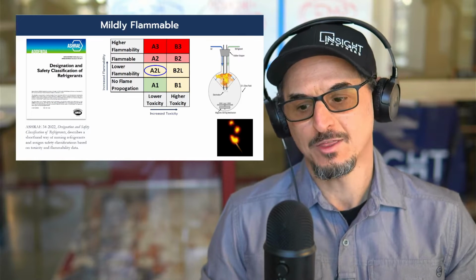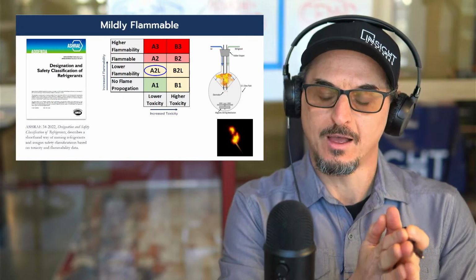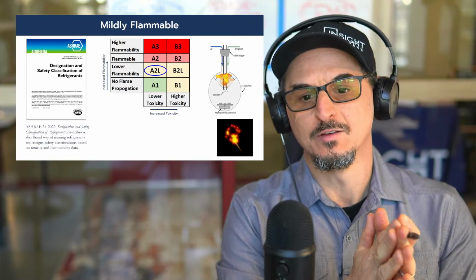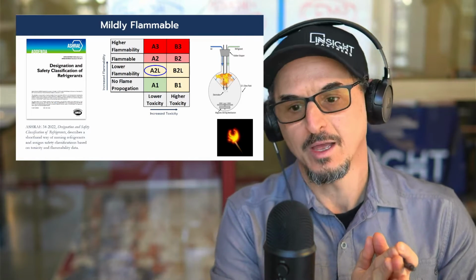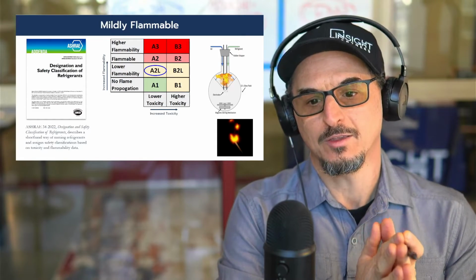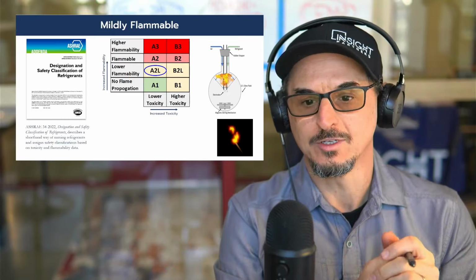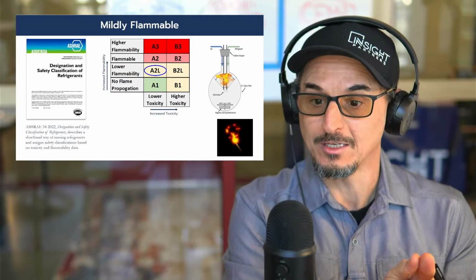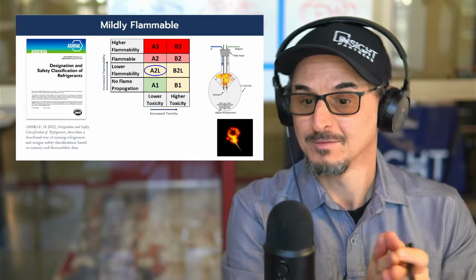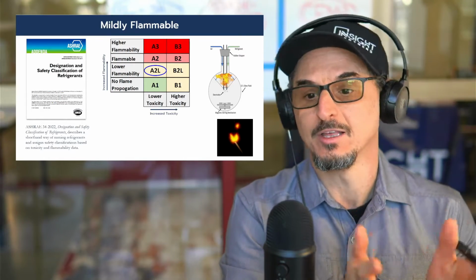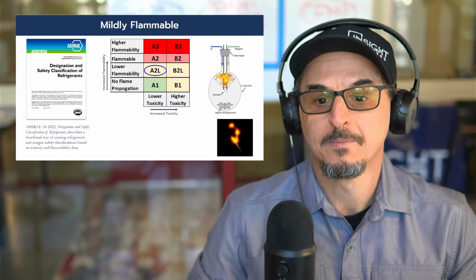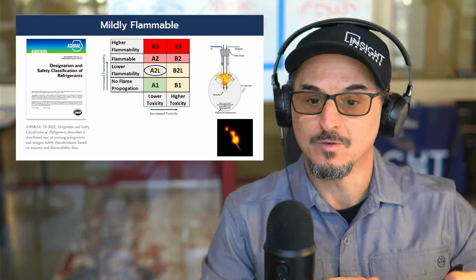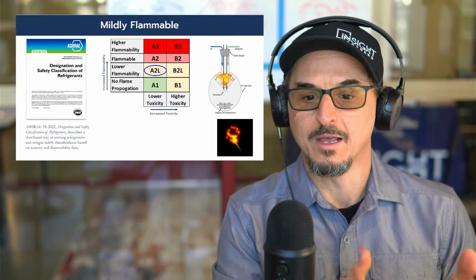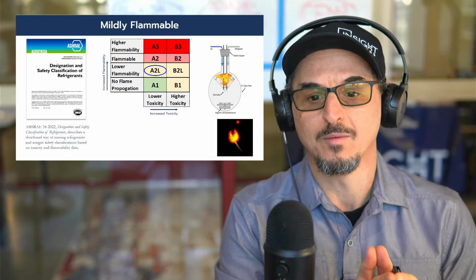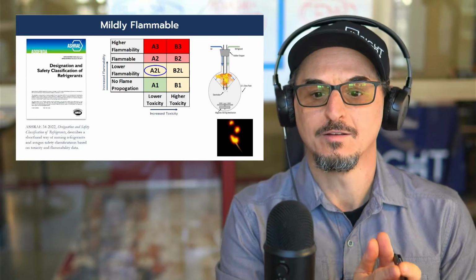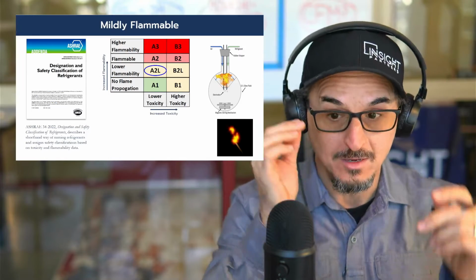ASHRAE 34 is what we use to classify the refrigerant in terms of flammability and toxicity. The X axis refers to toxicity - there's two classifications, lower toxicity and higher toxicity. I don't know exactly how they determine that, but basically higher toxicity is a little more dangerous if you get around it. Flammability is on the Y axis, from low to high. The way they rate it: no flame propagation, lower flammability, flammable, and higher flammability - those are the terms they use.